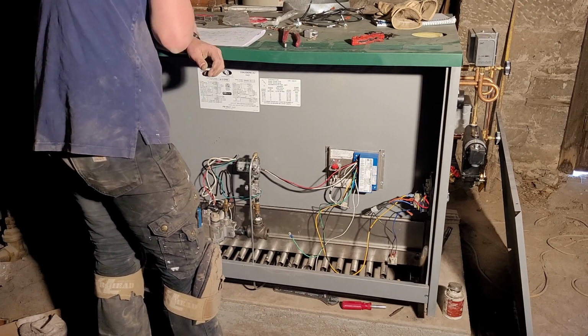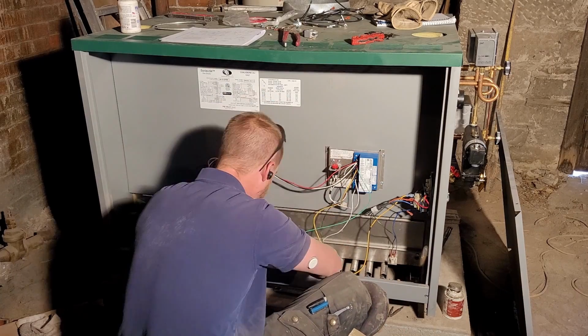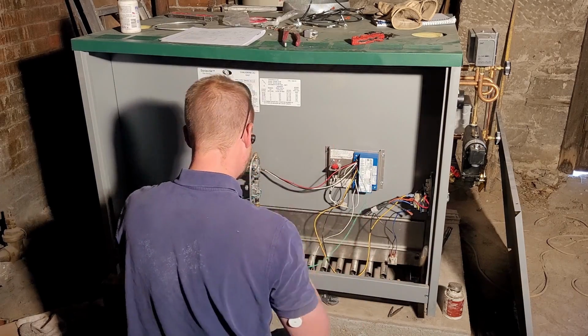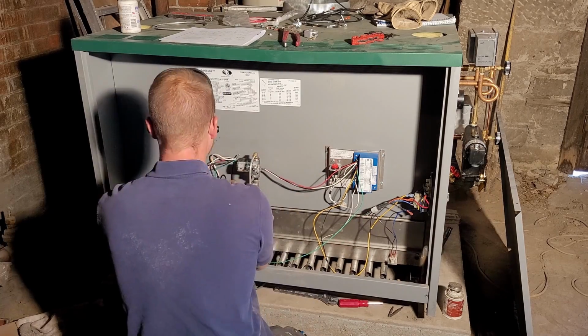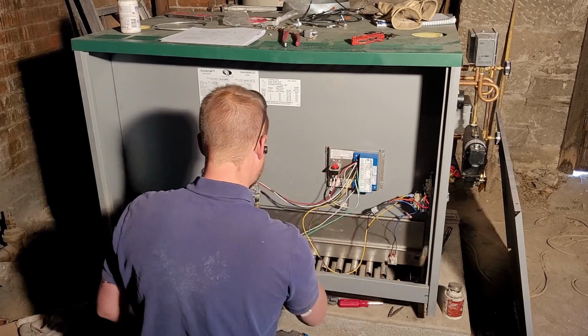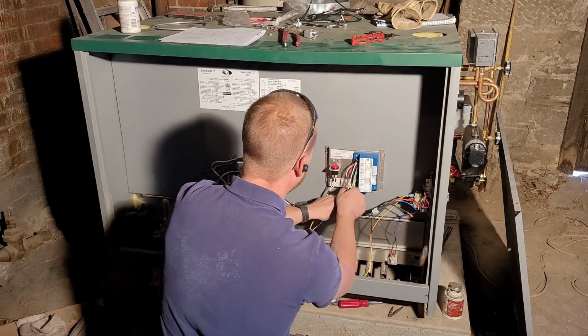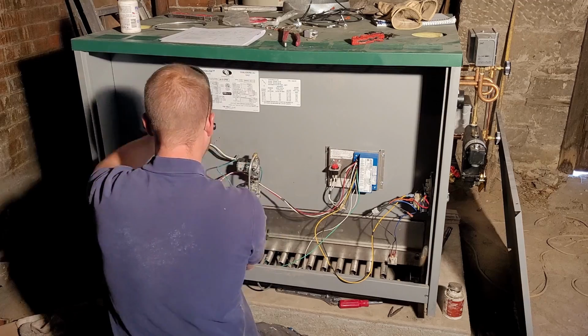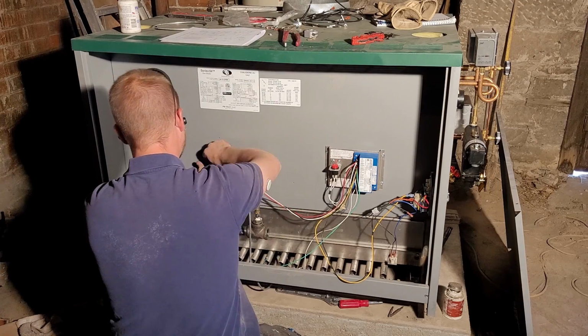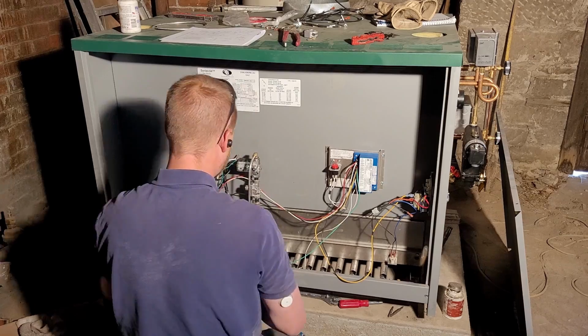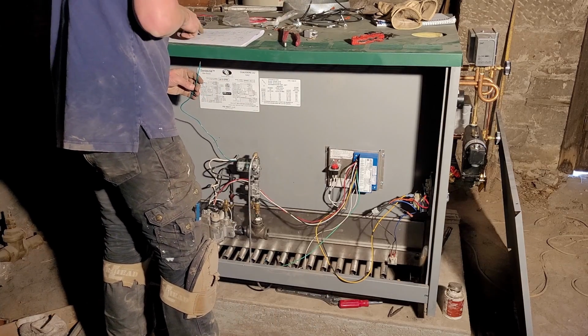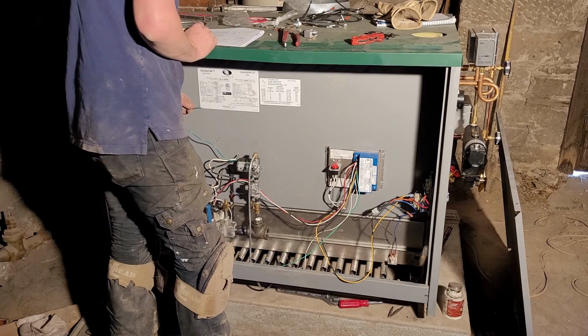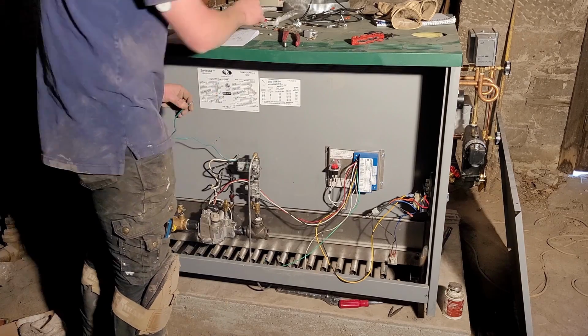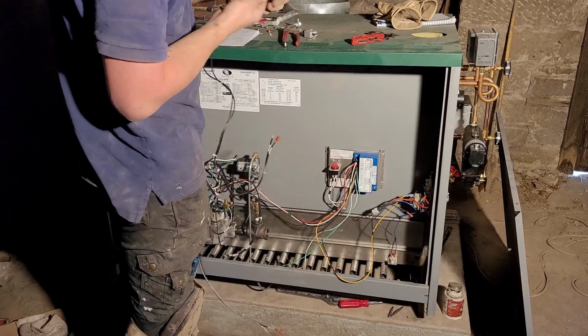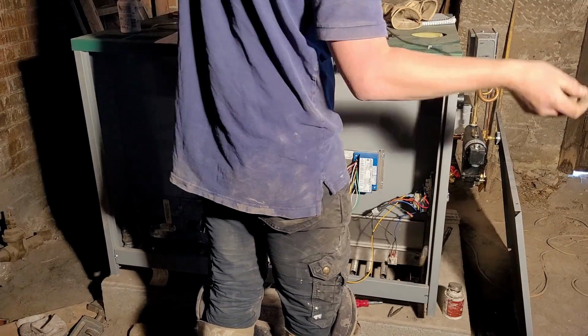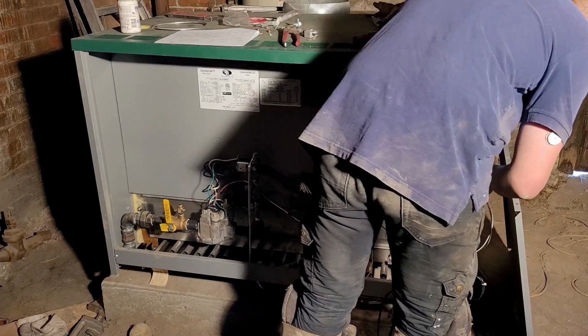So right now you'll see me constantly referring back to the instruction manual and following the wiring diagram, making sure I double and triple check. Not only am I hooking things up correctly according to their color, I'm also tracing back and making sure those colors are correctly connected, because I've run into it before where someone screwed up on the assembly line at the boiler manufacturer and had the wrong color wire in the wiring harness, and I had to shift stuff around to connect it correctly. So you always double and triple check, because if you hook this up wrong, you run the risk of blowing up a transformer or control, and then you have to deal with the delay in getting that part and all that stuff. So I don't want any mistakes.